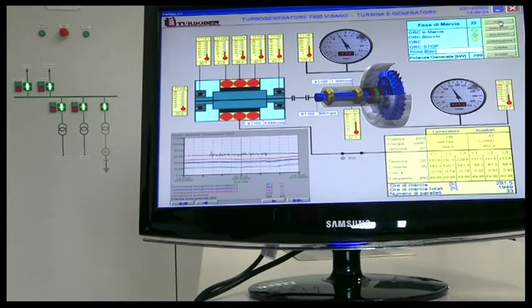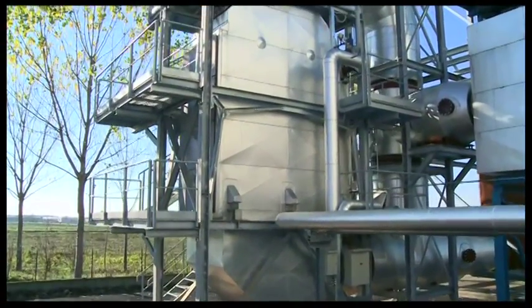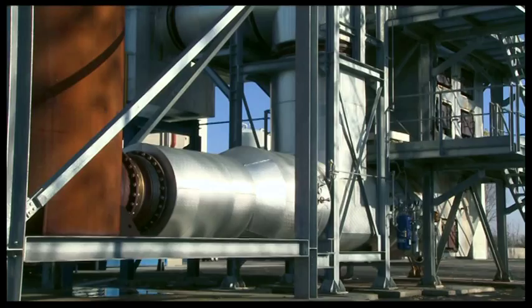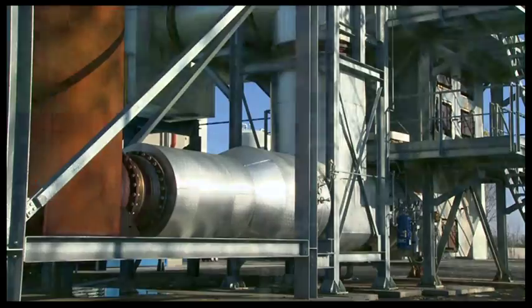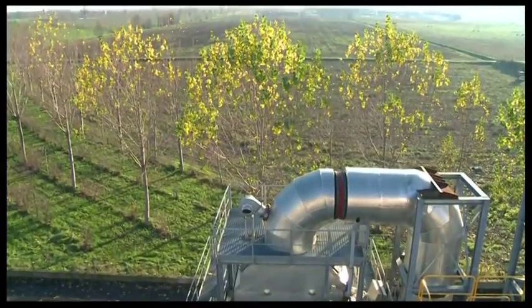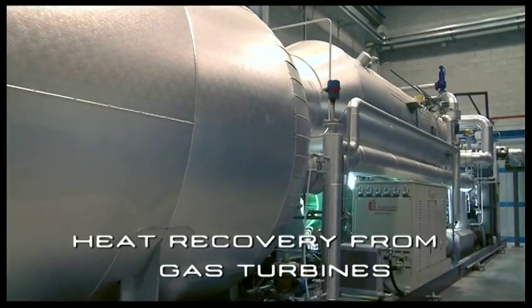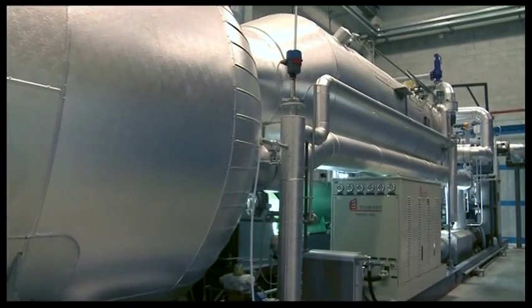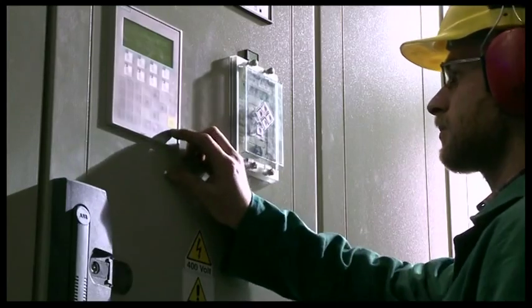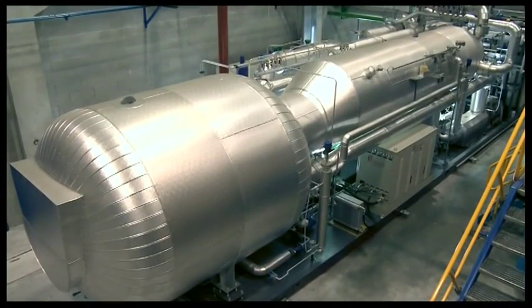In the field of heat recovery into combined cycles, the Turboden ORC modules are coupled to internal combustion engines fueled by natural gas, biogas from landfills, fermentation or gasification, fossil fuel oils such as diesel fuel or heavy oil fuel, or vegetable fuel oils such as palm oil and colza oil. Also the recovery from gas turbines and in particular in natural gas compression stations, the Turboden ORC modules can find an efficient use, thanks to the good electrical efficiencies coupled to the minimum requests of management and maintenance.